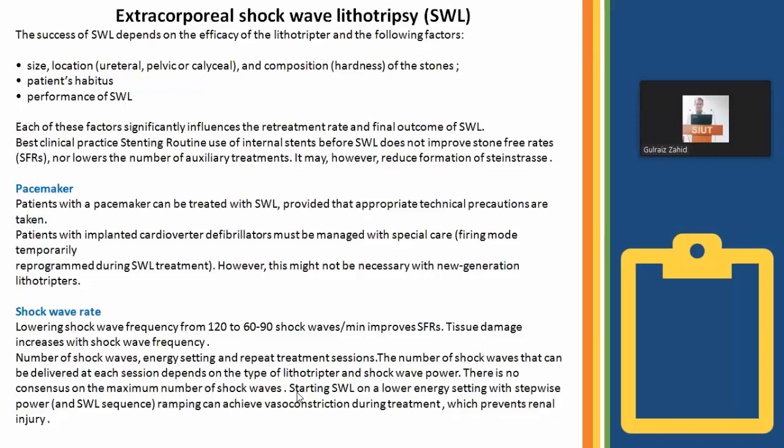Pacemaker. Patients with a pacemaker can be treated with SWL provided that appropriate technical precautions are taken. Patients with implanted cardioverter defibrillators must be managed with special care, and the device may need to be reprogrammed during SWL treatment. However, this might not be necessary with new generation lithotripters.